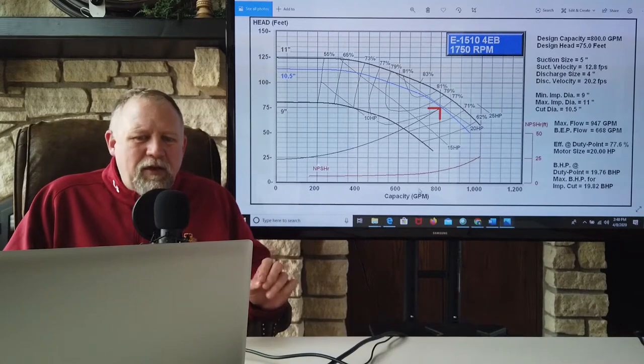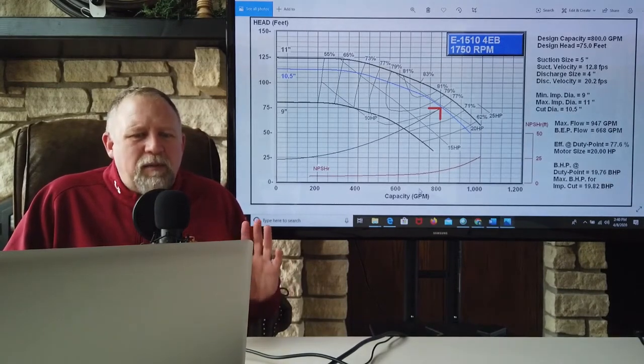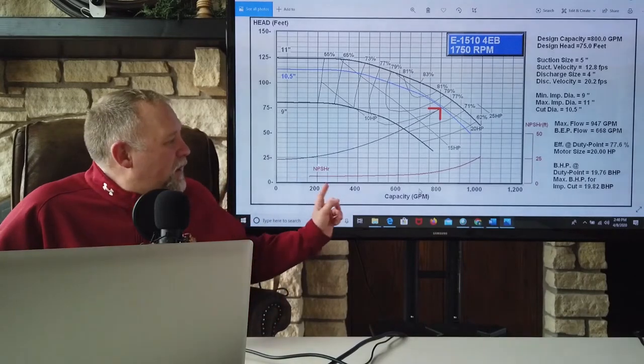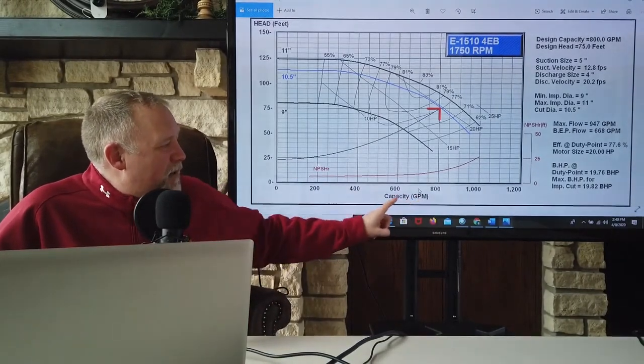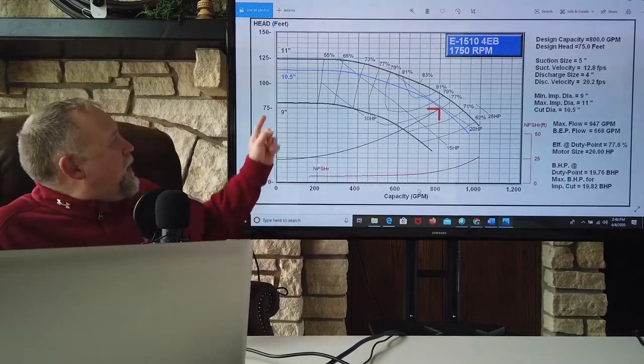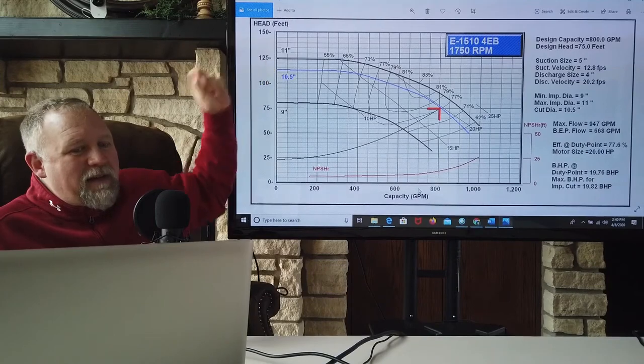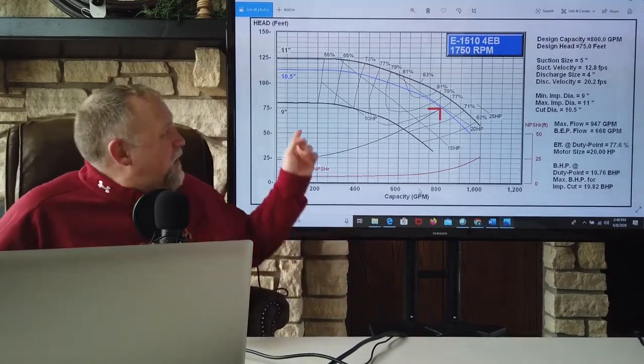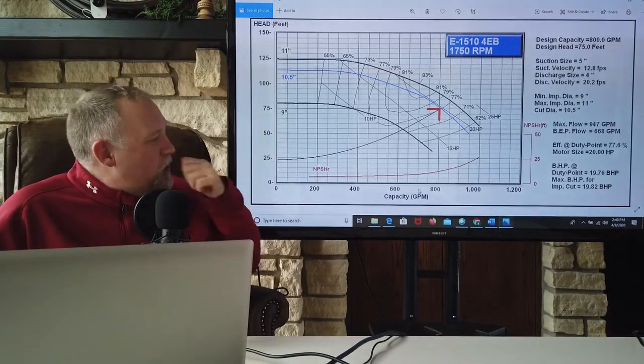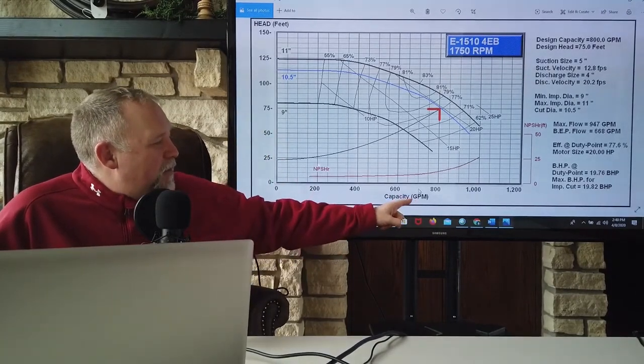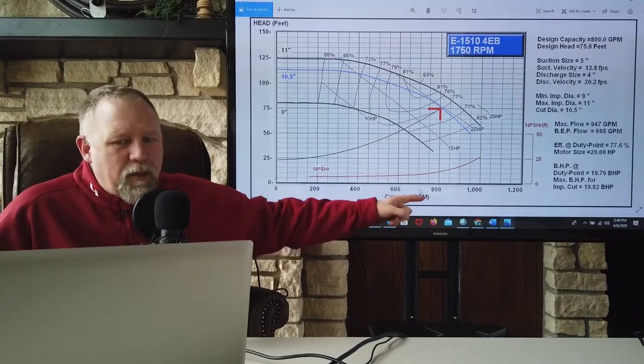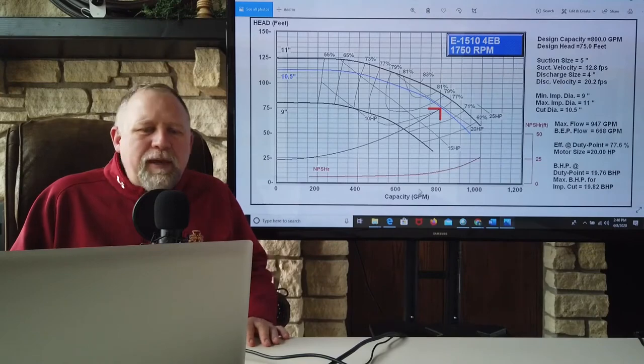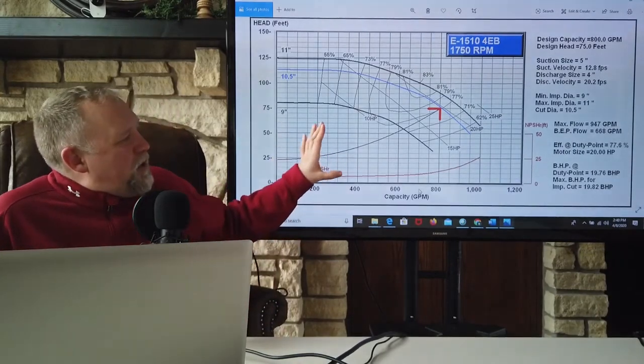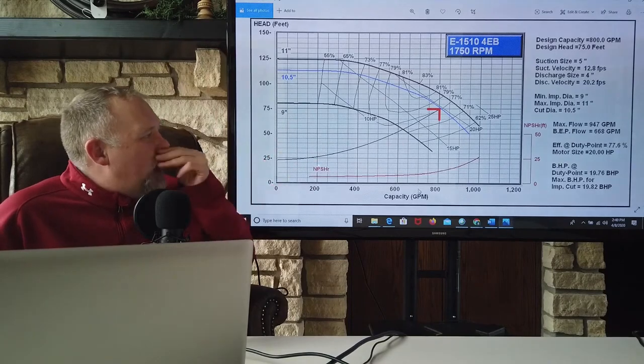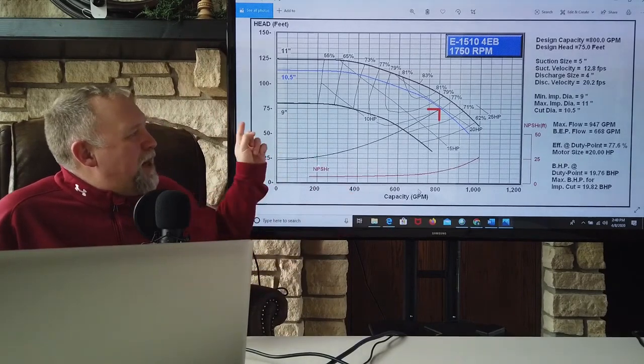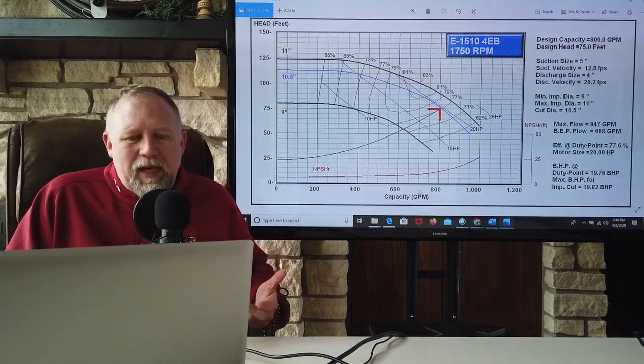I want you to think of this impeller curve as all of the possible combinations of flow in gallons per minute down here at the bottom and pressure. That's what this column here is, and we're going to list that in feet of head. This could also be PSI. It's a simple conversion that we've already looked at. This capacity could be, instead of gallons per minute, liters per second. It could be any volumetric flow rate. And this could be any pressure. But I want you to think of this graph as all of the possible combinations of flow rate and pressure that a certain pump can generate.